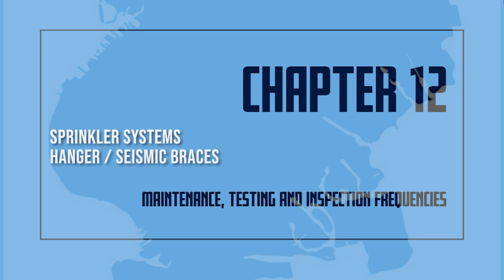Hangers/seismic braces. Hangers installed in concealed spaces such as above suspended ceilings shall not need inspection. Hangers installed in areas that are inaccessible for safety considerations due to process operations shall be inspected during each scheduled shutdown. Hangers and braces shall be inspected annually from floor level to ensure they are in place, properly aligned, and otherwise not damaged. All defects and deficiencies shall be corrected.